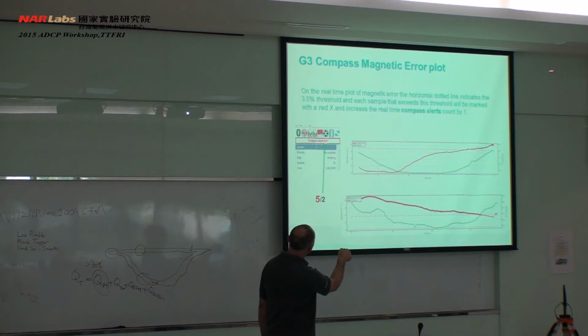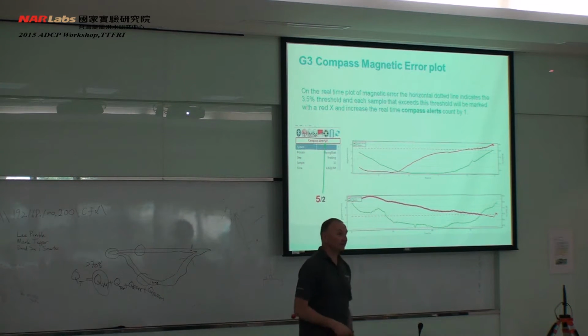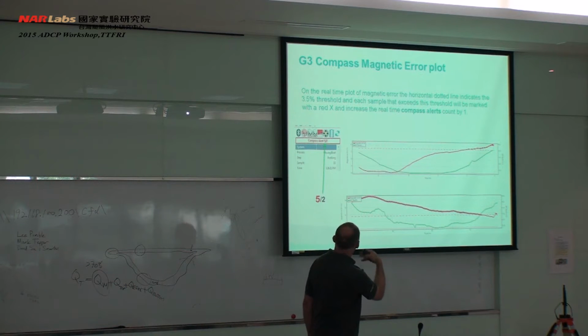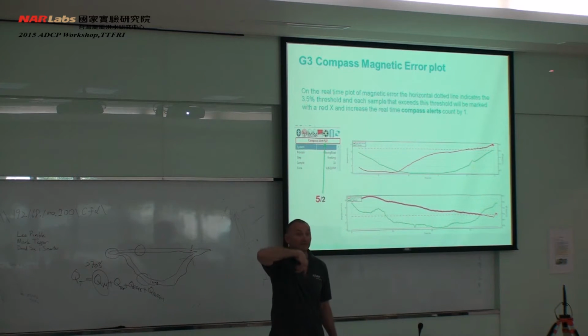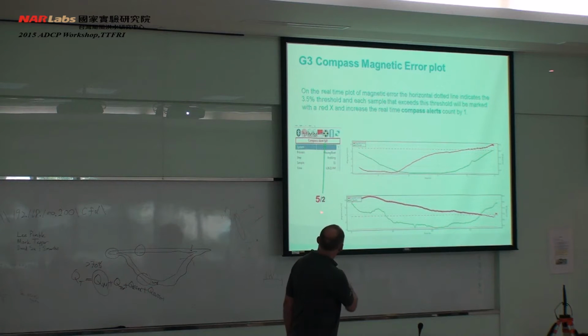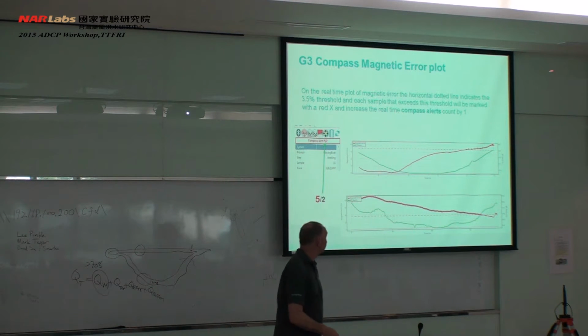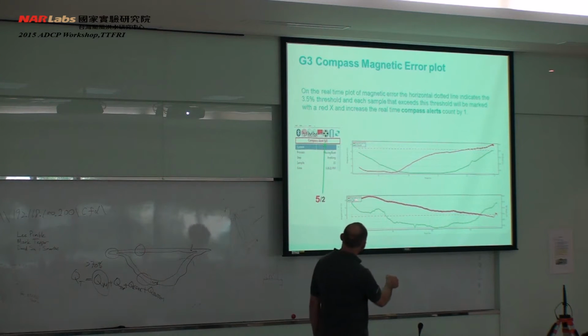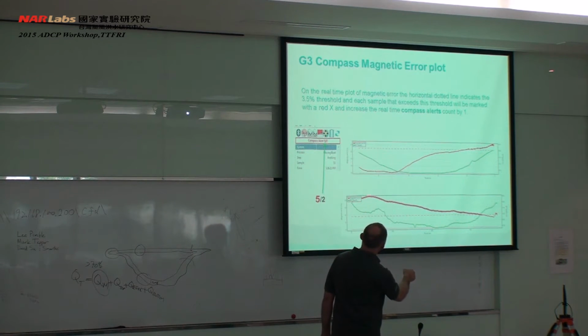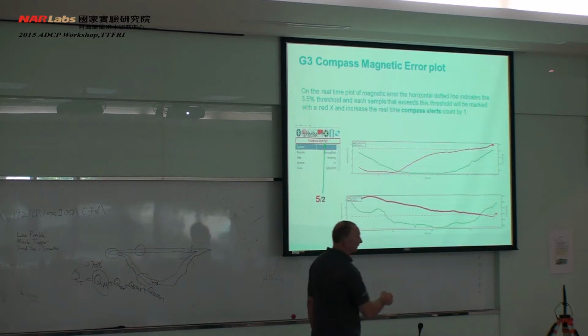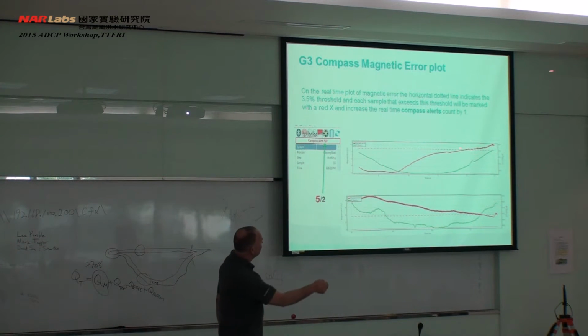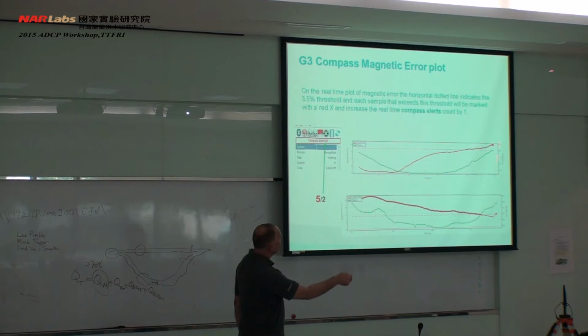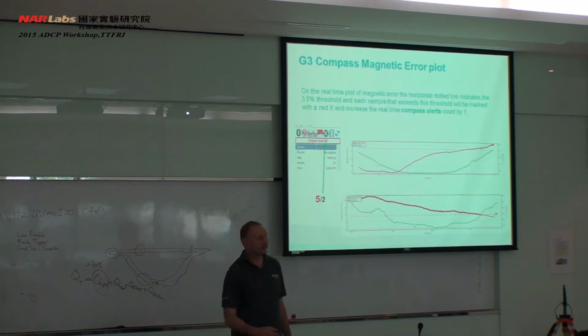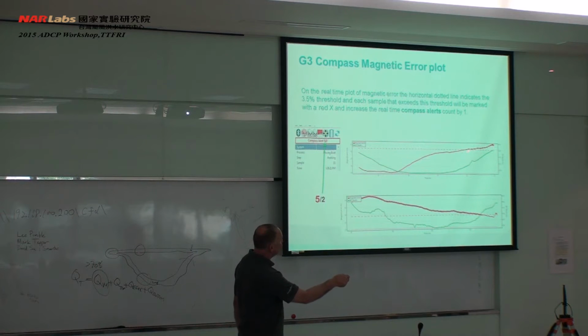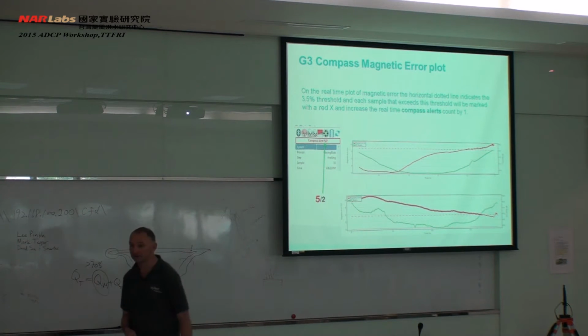The first number, the 5 in this case, is showing that we've got a compass alert from the magnetic field, and the second one is for the pitch and roll. So in this case, this data really is quite unacceptable for the compass. This has probably occurred because there's a concrete wall at the edge here with a lot of metal inside it, and as the instrument got closer and closer to that, it started to pick up that interference.